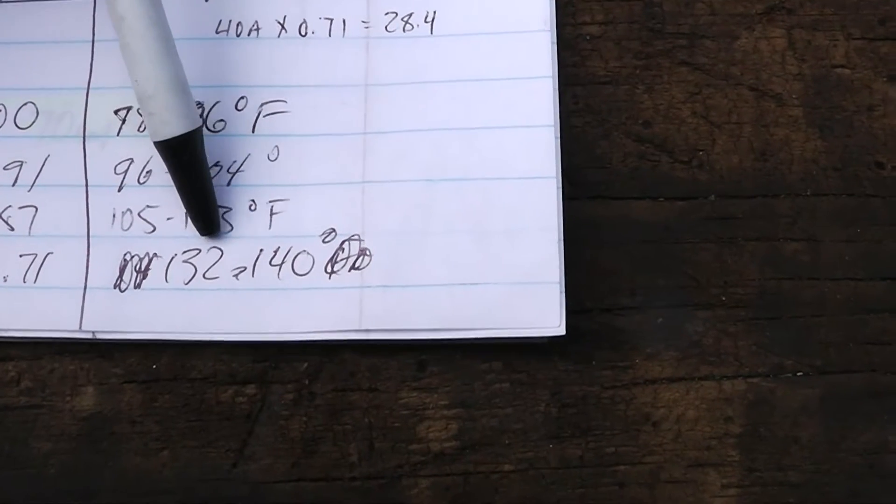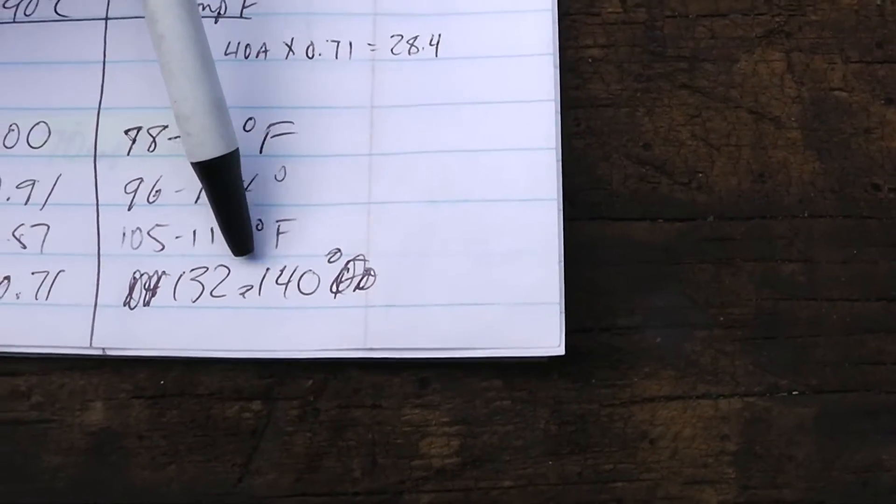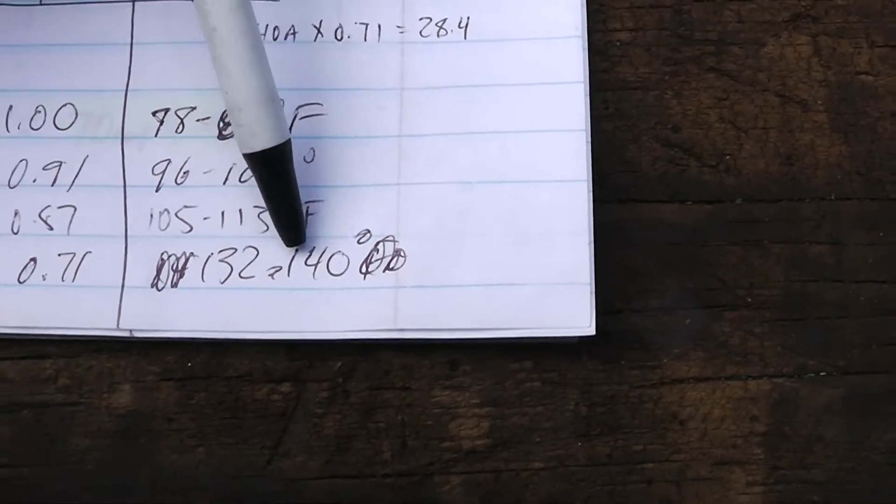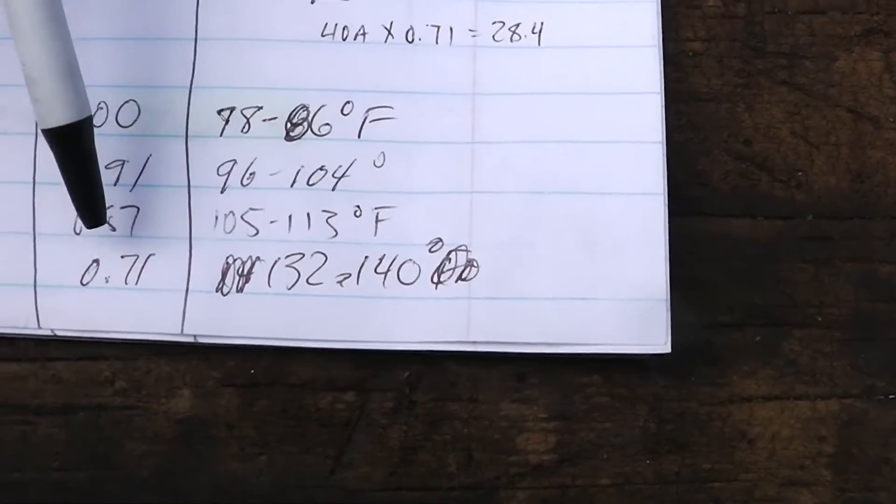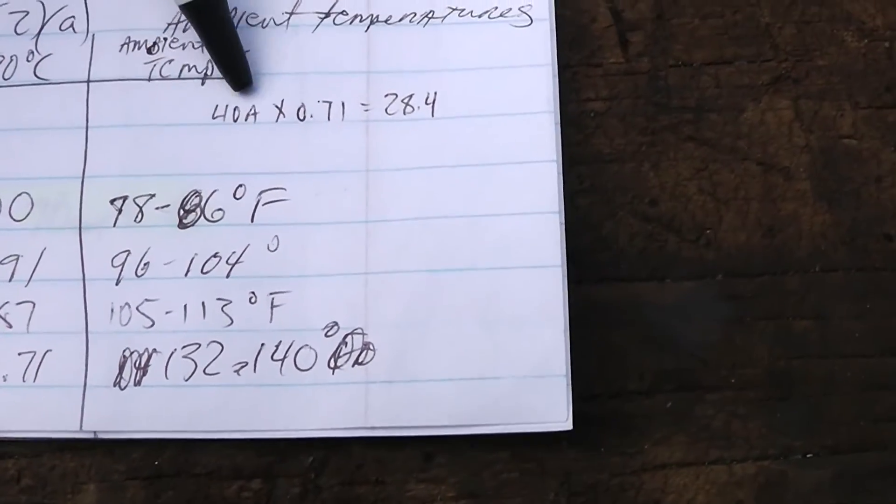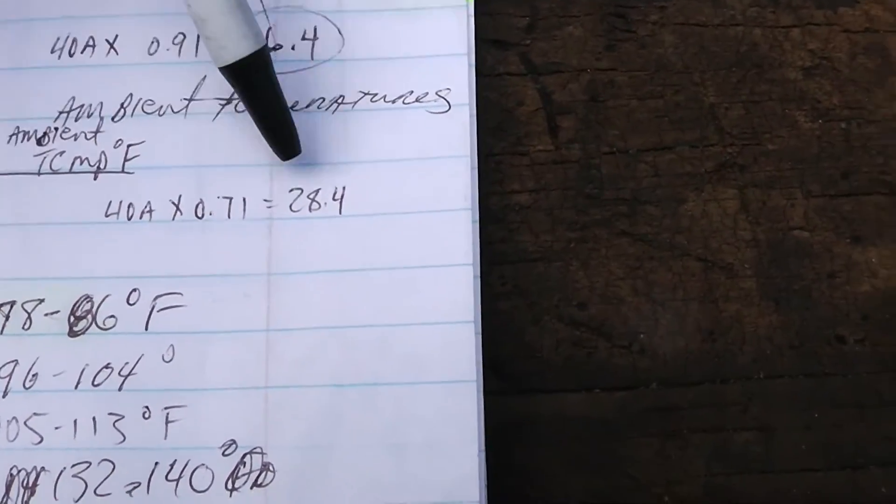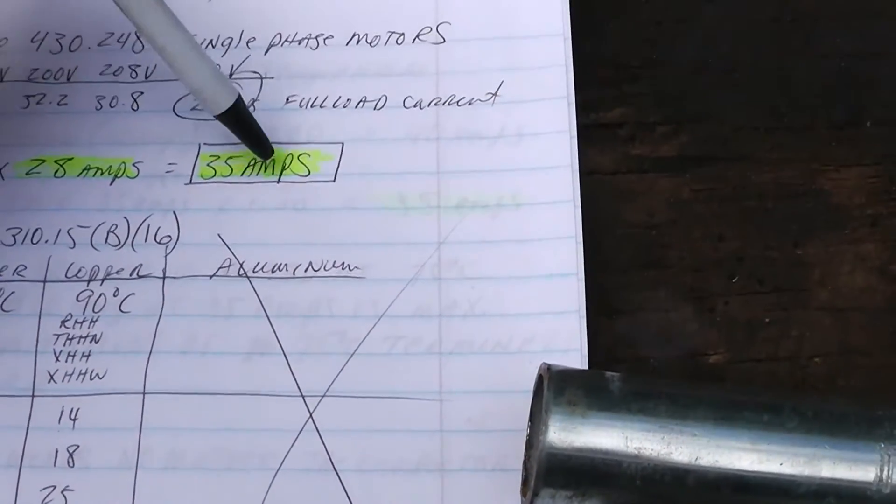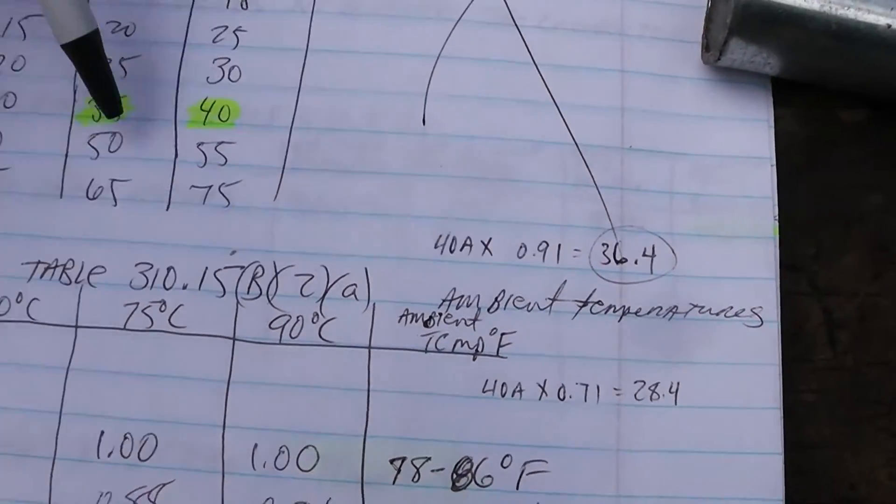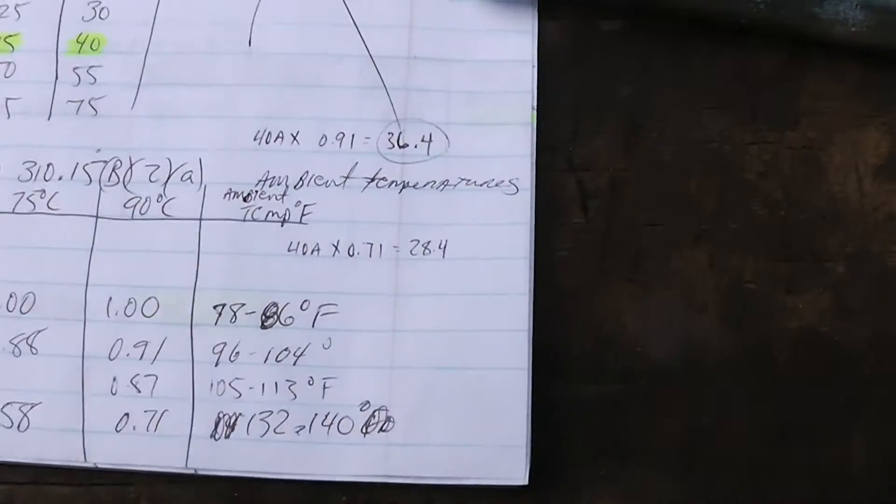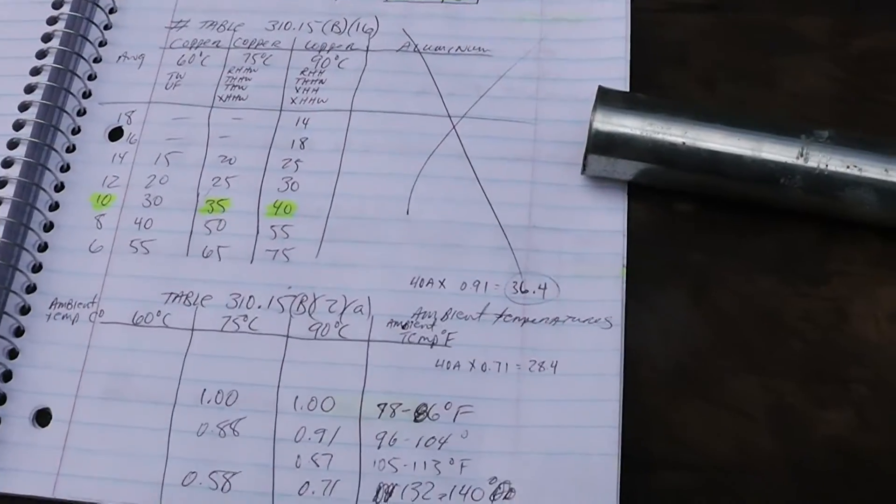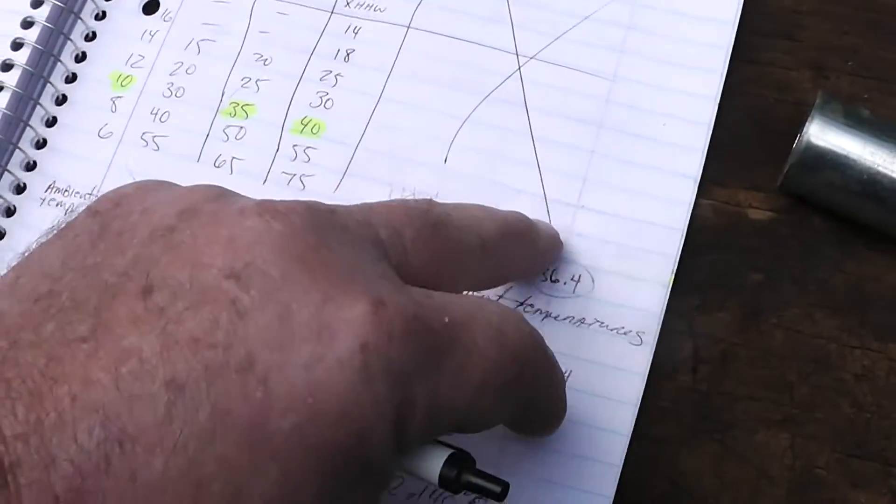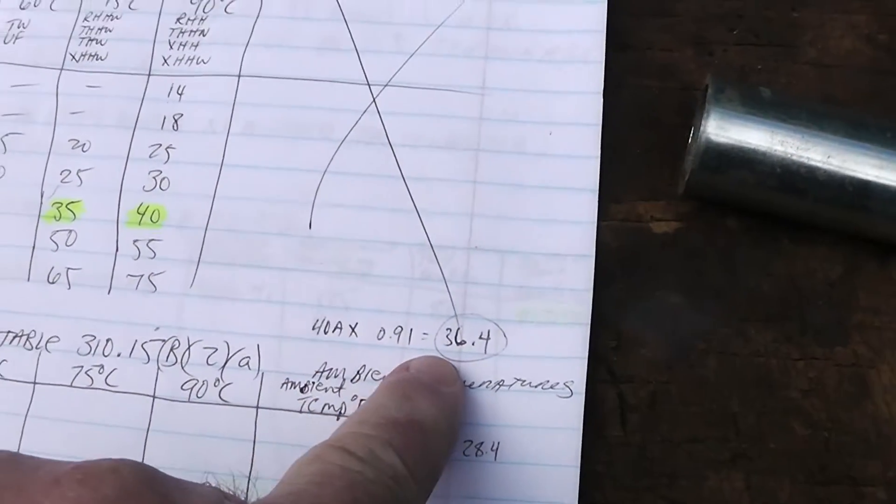If you're somewhere like Death Valley and you're in this ambient temperature range, you take that multiplier and multiply by the 40, and that gives you 28.4, which does not work. You have to bump the wire size up to a number 8 or number 6. So a number 10 at this temperature is not going to work.